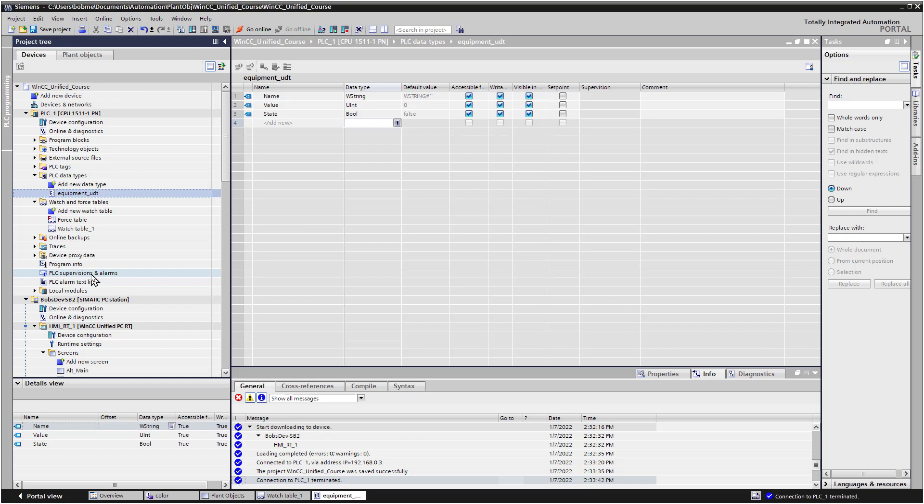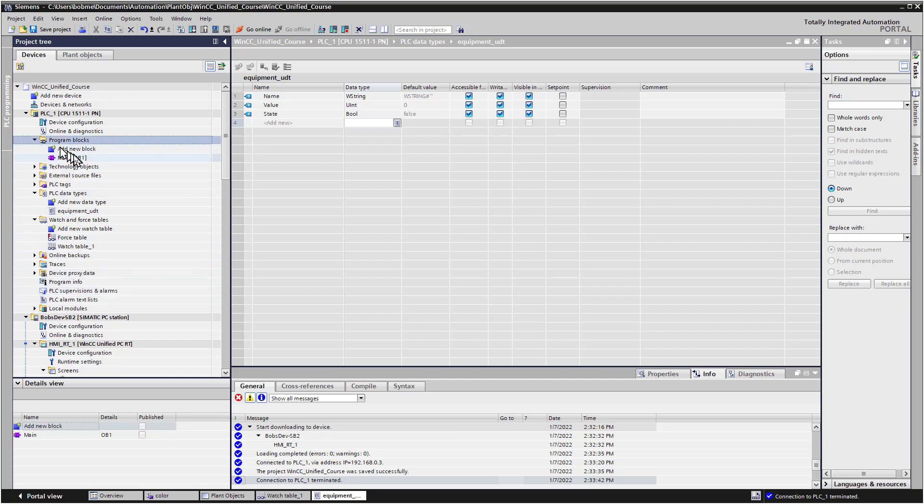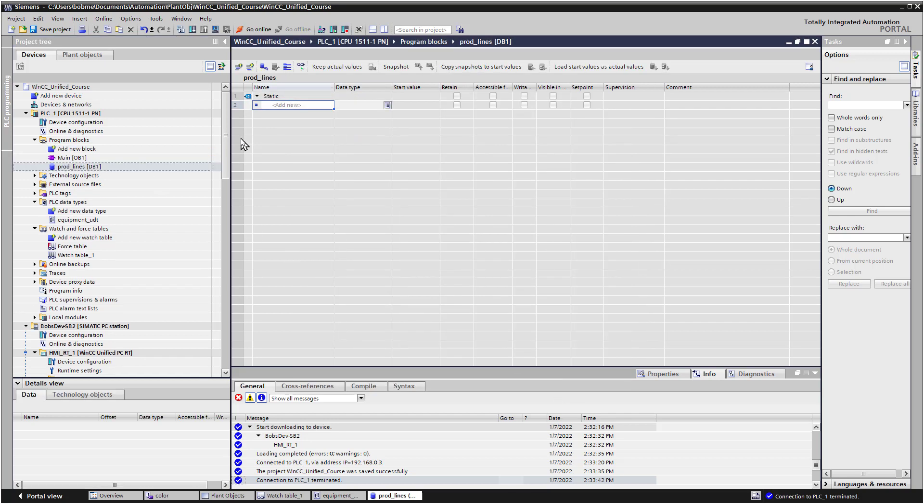Okay, so we've got a UDT now, and under Program Blocks, we're going to add a new block, and I'm just going to add a data block, and we're going to call it Production Lines, and just click OK. And we're going to create some instances, this Equipment UDT, for some conveyors and pumps and motors to represent different lines.